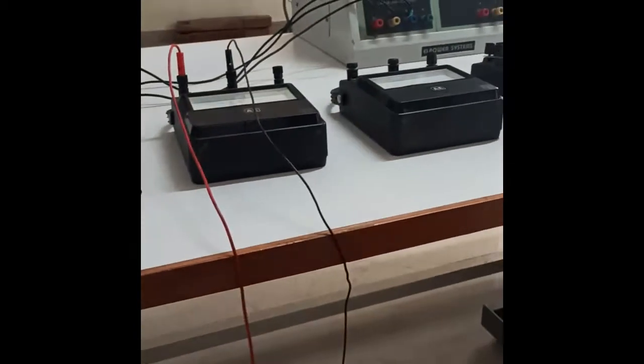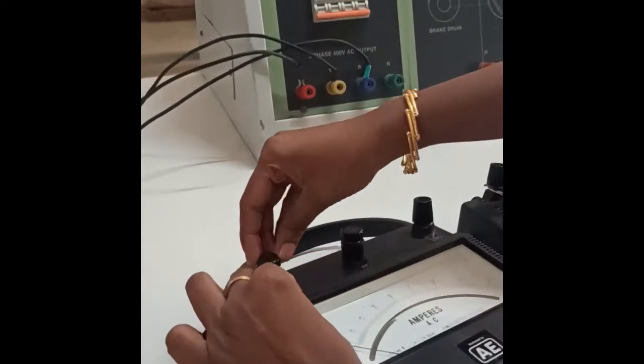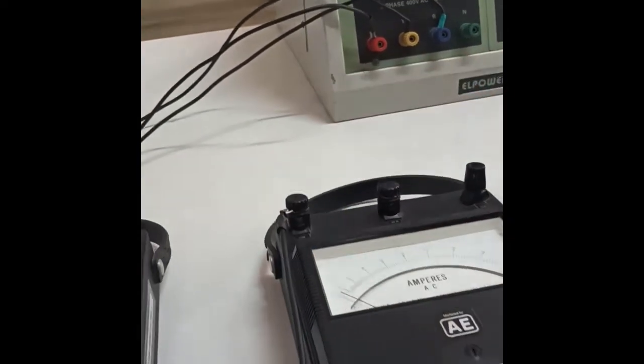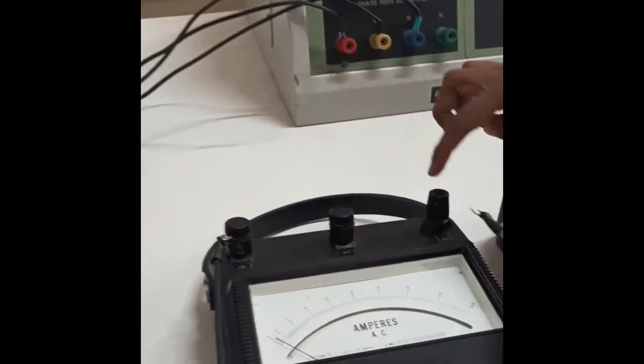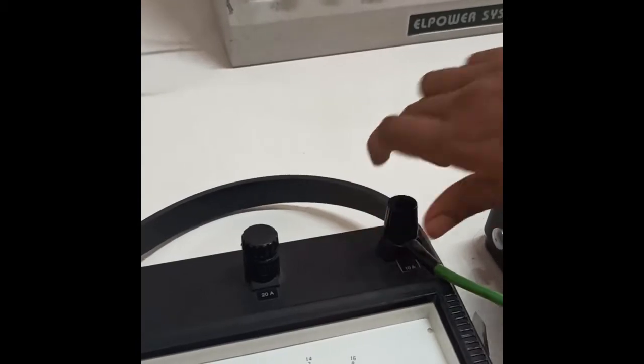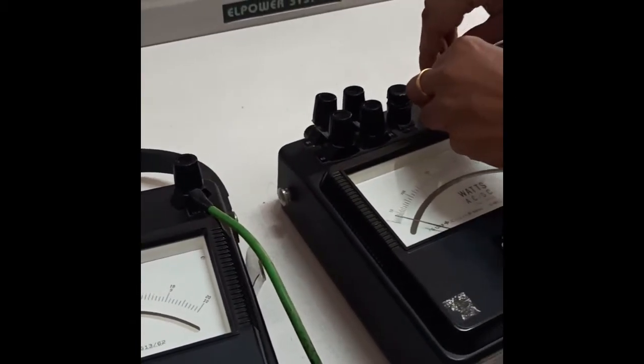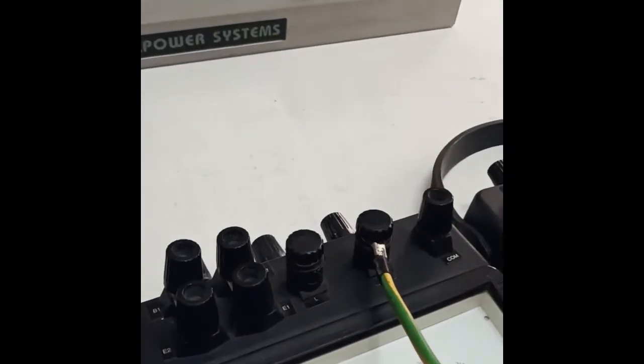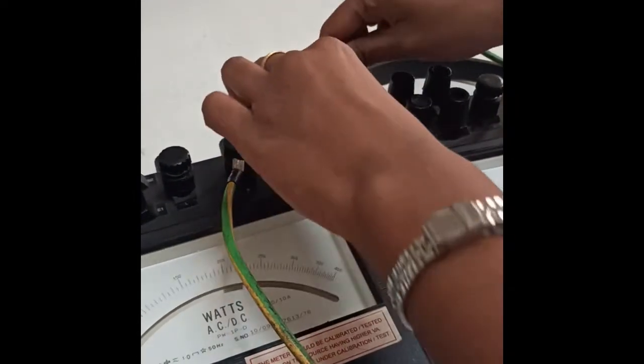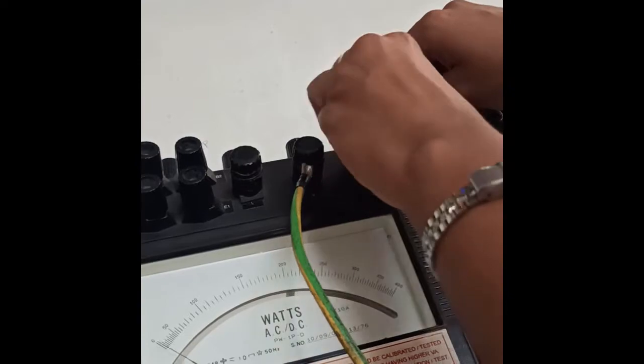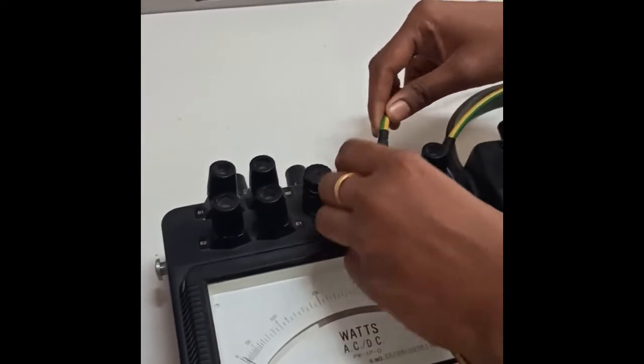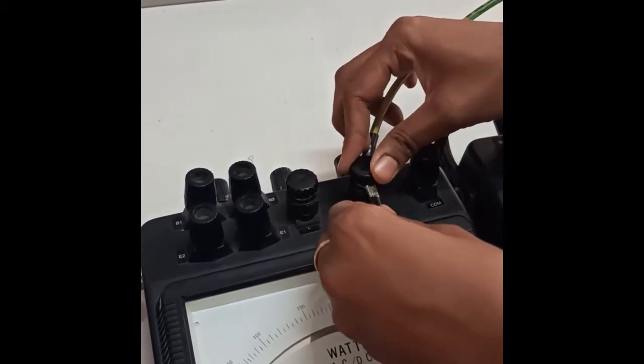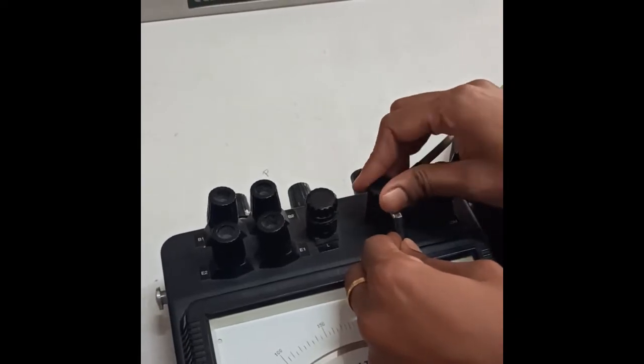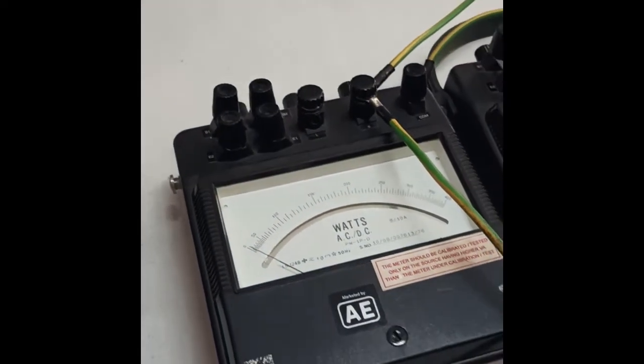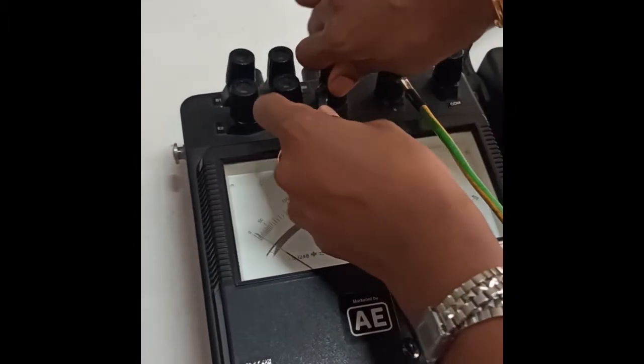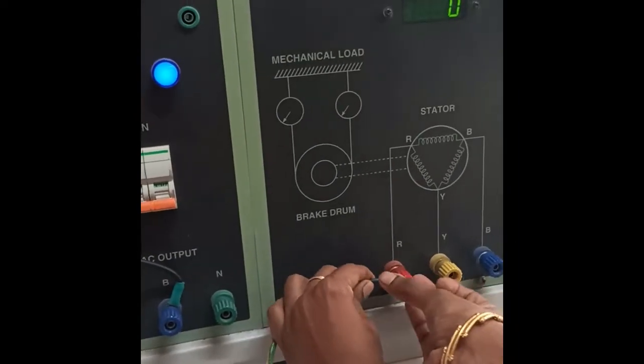So this R phase has to be connected to the ammeter. Now because this is AC, polarity is not bothered much. So we will connect to the ammeter. The other end of the ammeter, we are selecting 0 to 10 amperes, has to be taken to the wattmeter. So in the wattmeter we are connecting it to the M terminal. Now M and C of the same wattmeter should be shorted. We have two connections to the same terminal. One is from the common terminal of the same meter, whereas the other one is from the ammeter. And the L terminal should be connected to the R phase of the stator winding in the panel as shown in the circuit diagram.